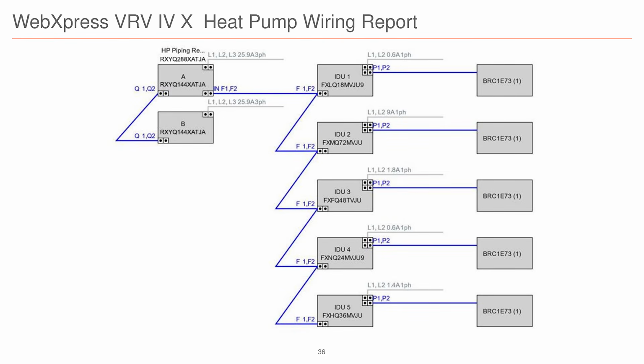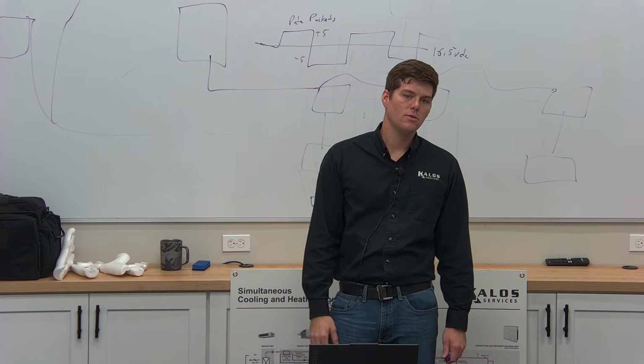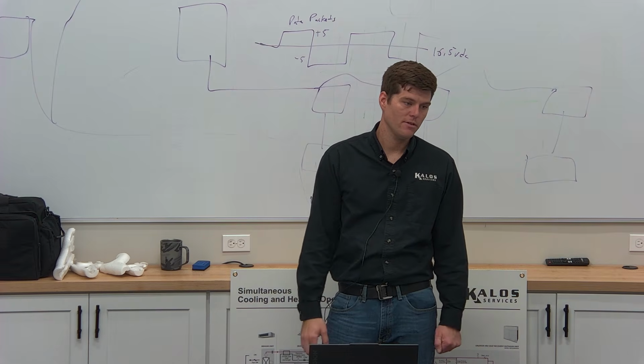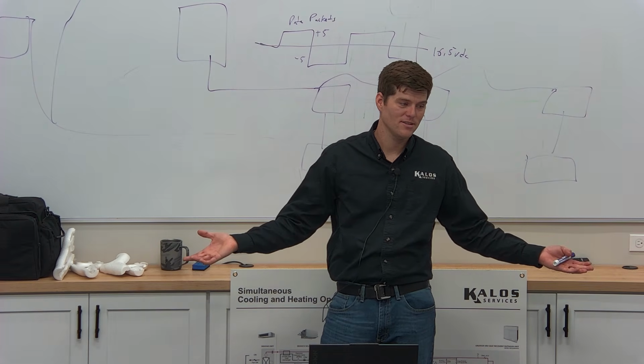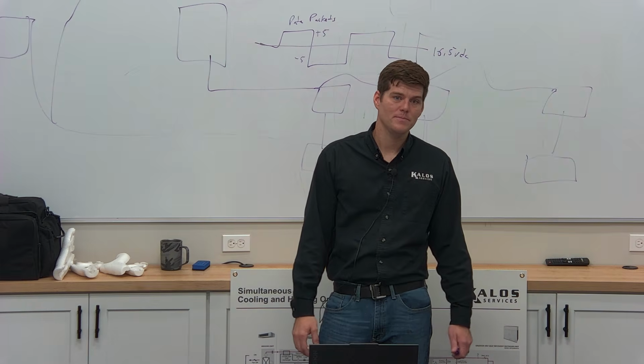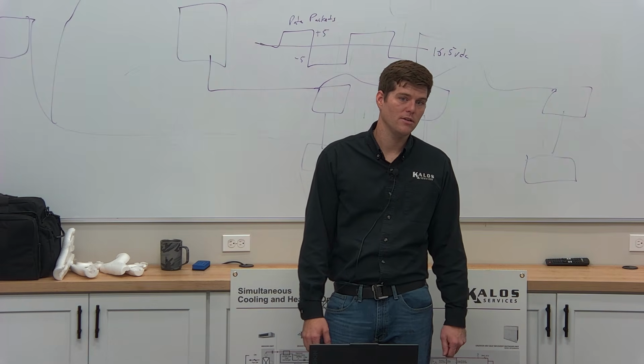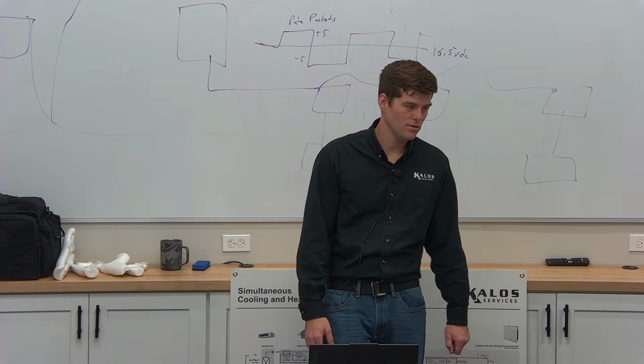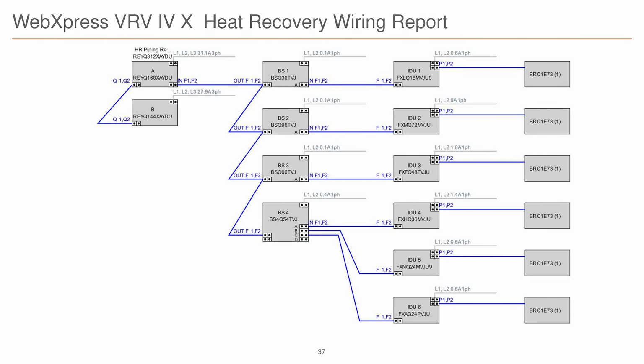Every job that you do with new construction or even retrofit, you will be provided with one of these. You'll know exactly what model number indoor unit, what model number thermostat, what tonnage, where in what position, and how to wire them. F1, F2 here, F1, F2 here, F1, F2 here. Oh, that's P1, P2 there. This is the wiring schematic for VRF. Not wildly complicated, guys. That's the outdoor units on the left. Yep, 2 outdoor units tied together, going to all these indoor fan coils with all these controllers. And this is with branch selector boxes.